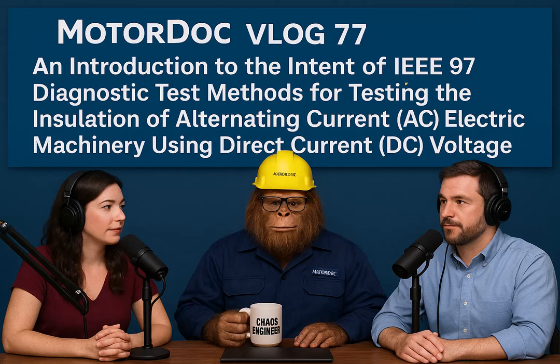Good quality test instruments are designed to minimize this internal noise and often have features to alert the user if noise levels are high. Field tests are more prone to this. Generally, yes. Field tests, especially if you're not connecting right at the motor terminals, can be more susceptible to picking up common mode noise. One last specific case.